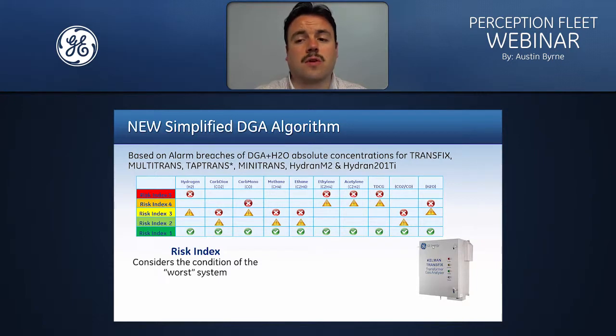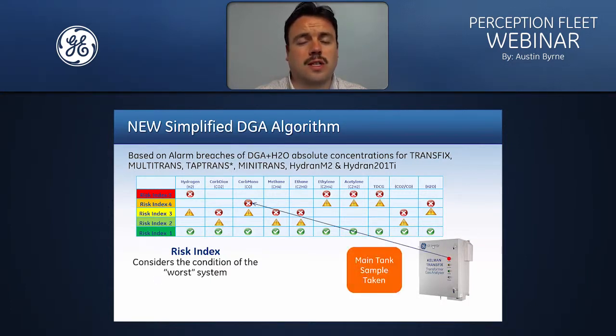We look at that for all the gases as well as the total dissolved combustible gas, ratios of CO2 against CO, and also moisture content. So whenever a sample is taken from the device, if an alarm is triggered, you can see an example on the screen, carbon monoxide has triggered a high alarm. The device is then given the risk index associated with that alarm. So for this example, it's a risk index of 4.